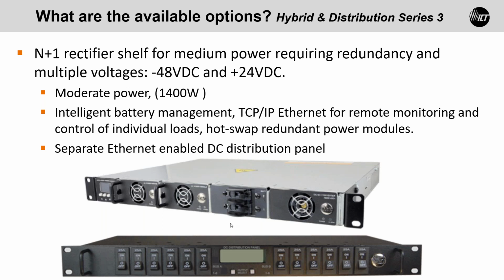So if you had a site that was like a 10 amp site, again you have N+1, and you also have a 24 volt supply. You could wire the neg 48 rectifiers into bus A of the distribution panel, and wire the 24 volt DC-DC converter into bus B. You'd have 6 breaker protected outputs for neg 48 and 6 breaker protected outputs for +24 in the same distribution panel. Very convenient - as far as I know, I don't think anybody else has this.